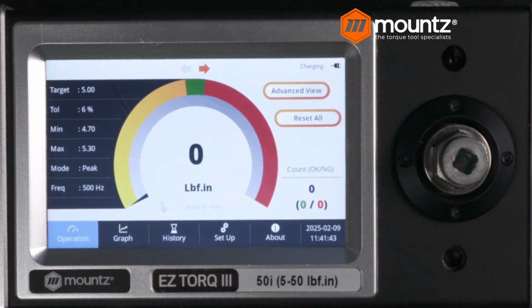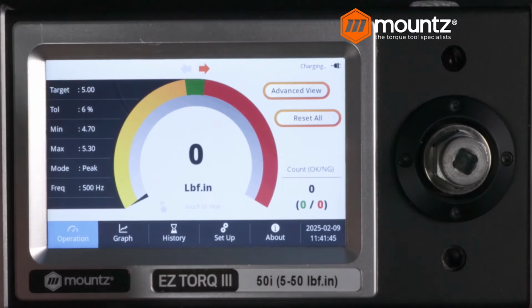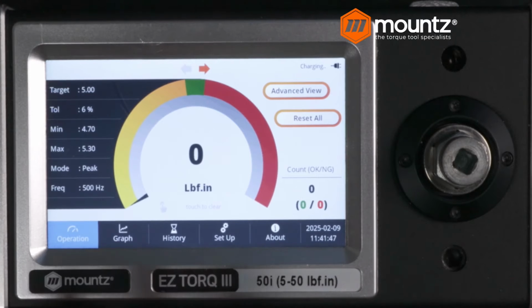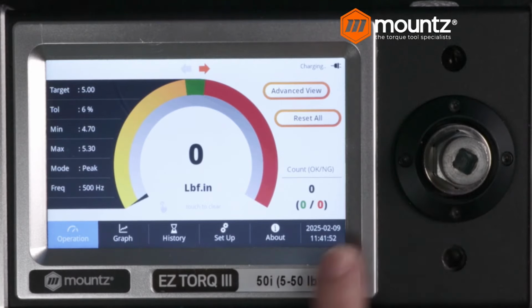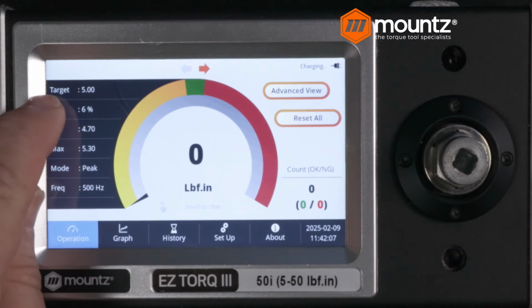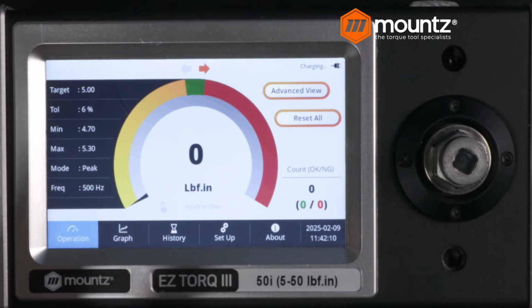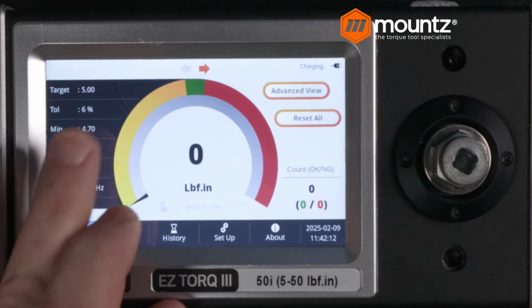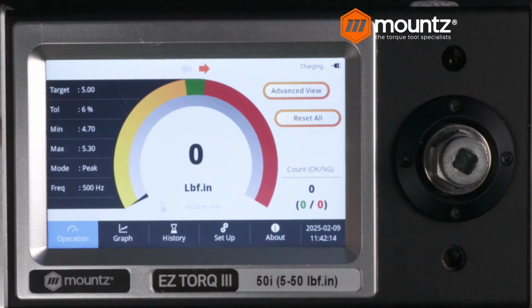Let's move a couple things here. All right, so we have our Easy Torque 3 torque analyzer. This analyzer has a built-in torque sensor here. It has a range from 5 to 50 inch-pounds. So we'll be testing a couple tools in that particular range. Now, to tell you what is going on here on the screen, we have the ability to set a target torque that we want to test to. We can enter in what our tolerance is. In this case, it's set to 6%.